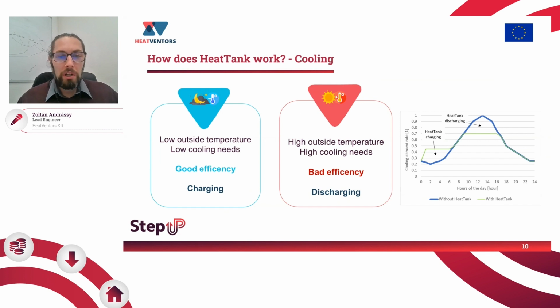So for cooling systems, and for every system that we are evaluating, we check how the system efficiency is changing, or what the dependencies of the system efficiency are. For a cooling system, when the external temperature is lower and when the partial load is optimal for the cooling system, then we have the best efficiency. So it's a good idea to generate more cooling energy with low outside temperatures and optimal partial loads of the system. And when the external temperature is increasing and the partial load is not right, we are able to discharge the storage. To the right, you can see a typical operation for an office building, where during the morning time we are able to charge the heat tank with a very good efficiency, and during the afternoon, when there is the peak need, we can discharge it.